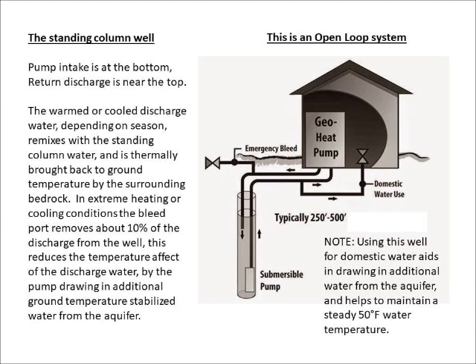The pump intake is at the bottom. The return discharge is near the top. The warmed or cooled discharge water, depending on season, remixes with the standing column water and is thermally brought back to ground temperature by the surrounding bedrock. In extreme heating or cooling conditions, the bleed port removes about 10% of the discharge from the well. This reduces the temperature effect of the discharge water by the pump drawing in additional ground temperature stabilized water from the aquifer. And note that using this well for domestic water aids in drawing in additional water from the aquifer and helps to maintain a steady 50 degrees Fahrenheit water temperature.